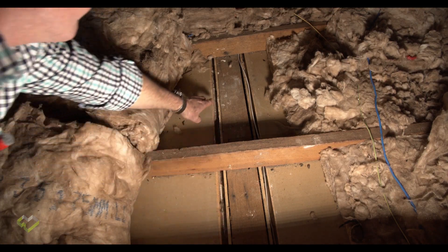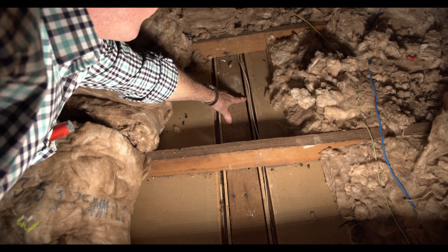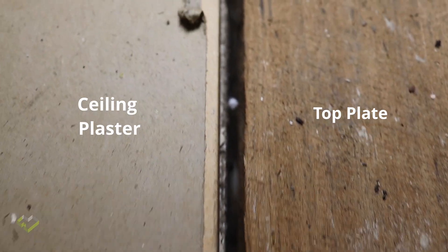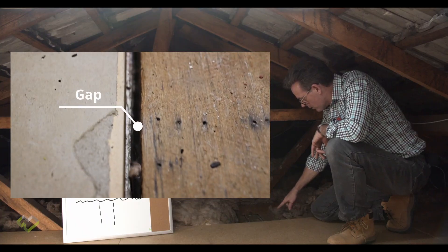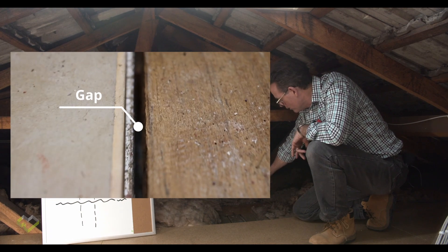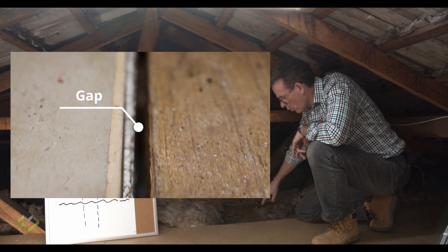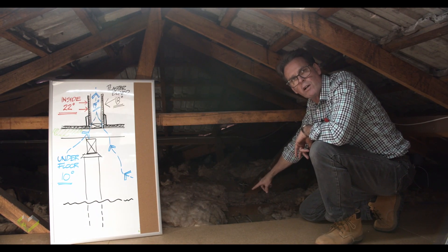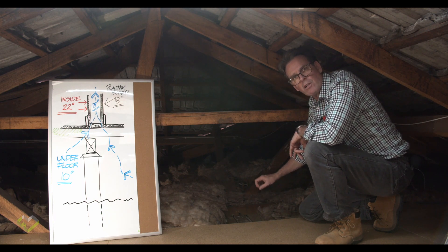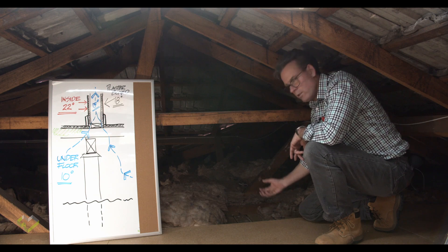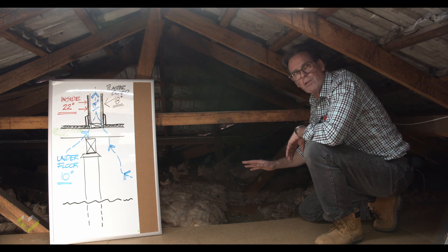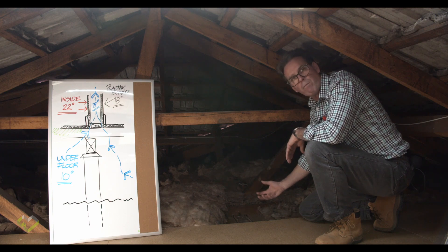We've peeled back the insulation in this roof — which is quite a well-insulated roof — but you can see the top of the wall. This is the wall of the passageway below, and either side of the top plate you can see two, three, even five millimetre gaps all the way along the top of this wall. That's the sort of gaps that are allowing the cold air from the subfloor to infiltrate straight up through the walls into this roof space.